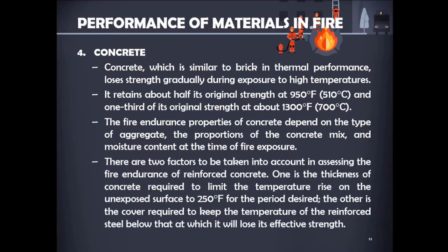There are two factors to assess in the fire endurance of reinforced concrete: one is the thickness of concrete required to limit temperature rise on the unexposed surface to 250°F for the desired period, and the other is the cover required to keep the temperature of the reinforced steel below the point at which it will lose its effective strength.